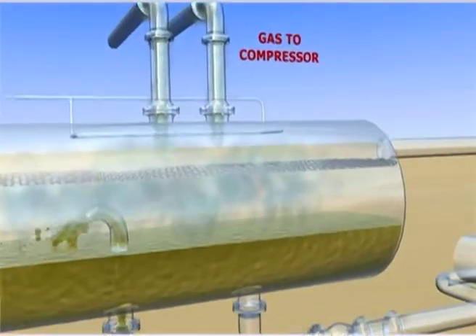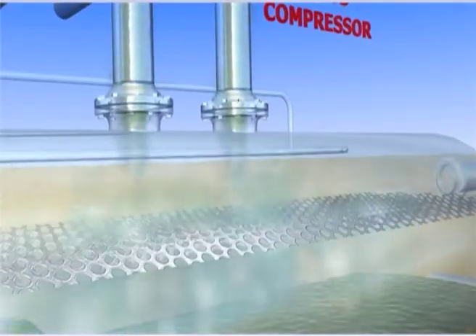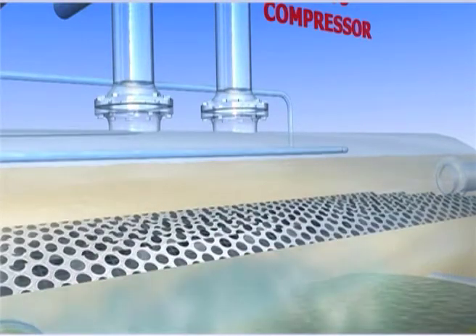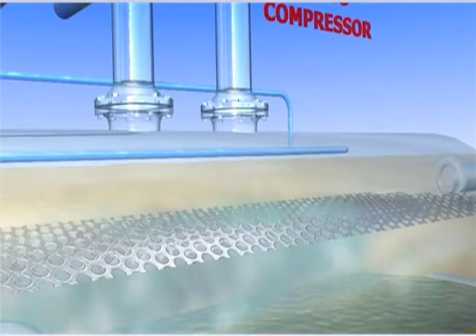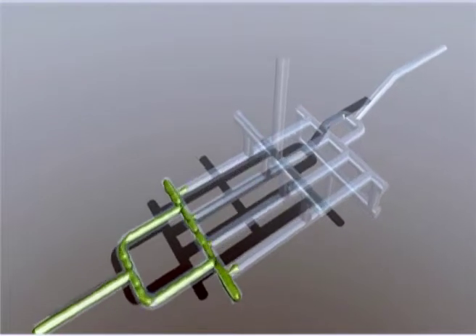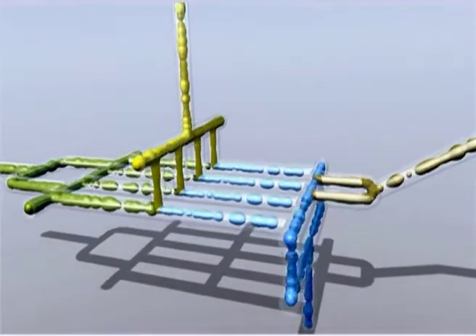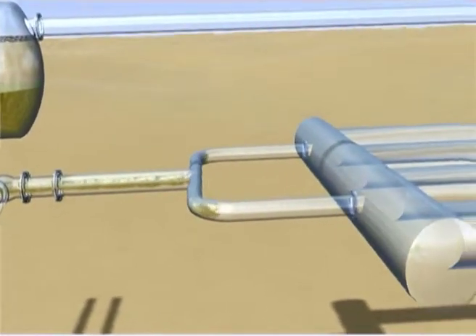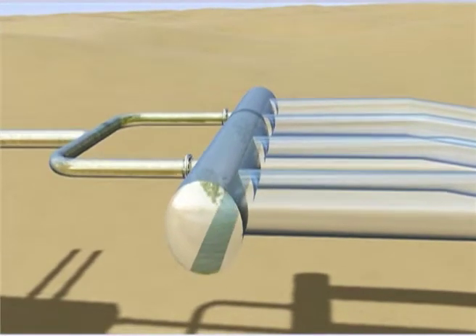The primary function of the dry gas risers is to deliver dry gas back into the system. The storage harps hold the liquids at line pressure, and the number and length of these harps is determined by the storage requirements, slug size, and residence time. The liquid and sludge manifolds provide separation of the water, oil, and debris.